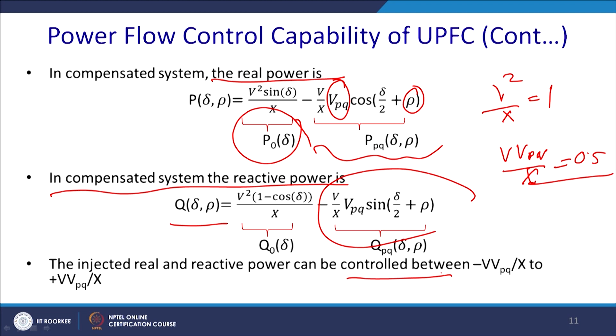So, now what happens is that the value Q of delta and rho will be given by V square by x, 1 minus cos delta, that is the uncompensated one, plus or minus another term that will come, that is V by x V_pq sin delta by 2 plus rho. So, we can see that we can inject real and reactive power control between minus V_pq by x to plus V_pq by x. Generally this magnitude we consider to be 0.5 per unit.